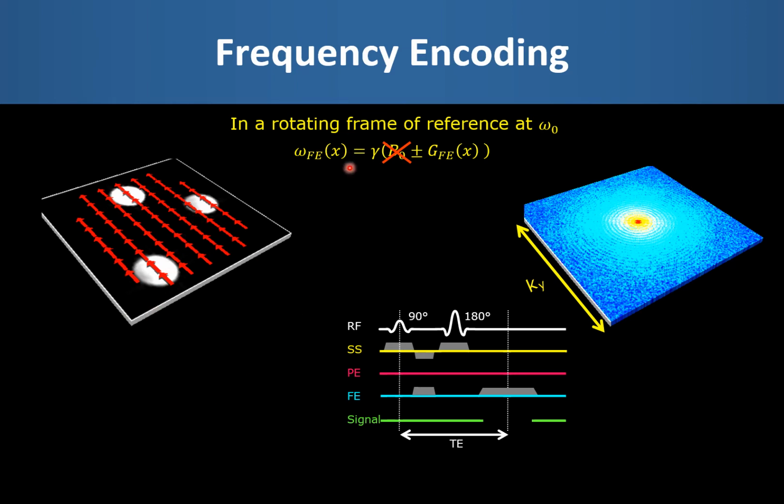If we work in a frame of reference also rotating at the Larmor frequency, then we can represent the spins at each sample point as a vector that appears stationary. Please ignore the fact that in reality the only signal producing areas would be the bottles, and accept that all the vectors have the same length, i.e. we will ignore all relaxation effects. So following the excitation pulse, the vectors will have 0 phase differences, and therefore we can consider them to be at the center of K-space.